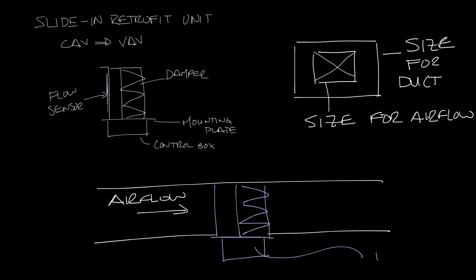And so now it works like any other VAV box. The controller is connected to a thermostat in the space, and it modulates the airflow to the space to maintain setpoint. That's how you can quickly turn a constant volume system into a VAV system using a QCV.